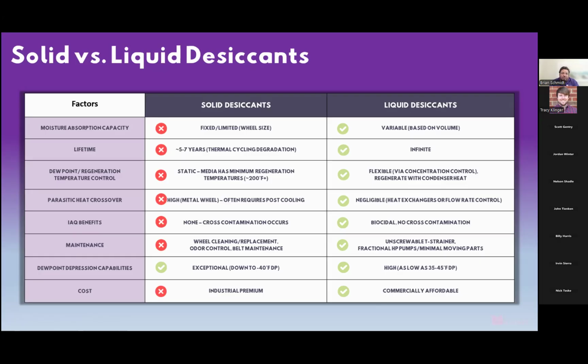Dewpoint and temperature control. In a solid desiccant, this is static. The media has a minimum regeneration temperature. So we do have to see very high temperatures for those. Versus a liquid desiccant where it's flexible, again, based on that concentration, and we can regenerate with condenser heat. And I'll show you that in a little bit. We need far less heat to evaporate the moisture out of these liquid desiccants than you would for a solid desiccant. There's also no parasitic heat crossover versus a solid desiccant wheel.